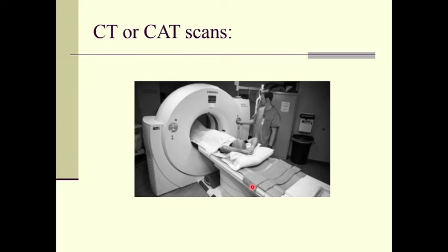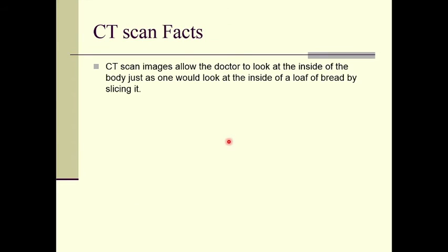So, this is a typical CT scan machine used to detect any anomalies in the patient. The patient is passed inside this chamber. This is a circular ring shaped CT scanner, right? Inside, the detector and X-ray source will be continuously rotating around the patient, and therefore it can take the axial picture of the patient's body, right.